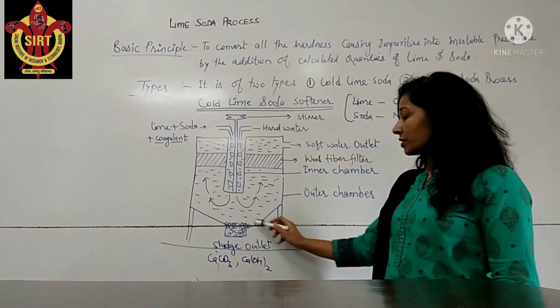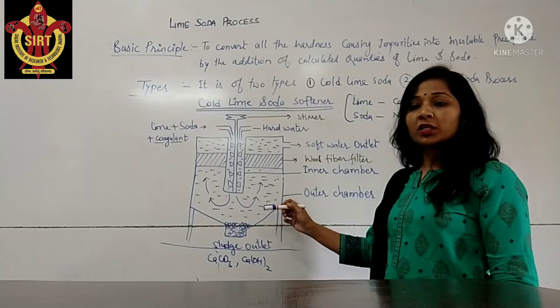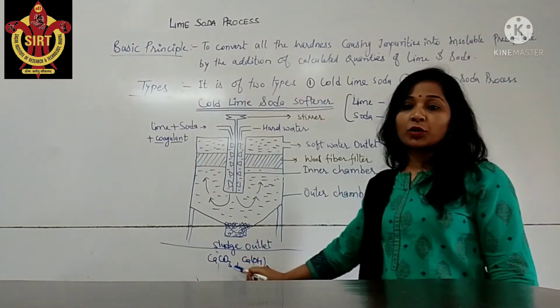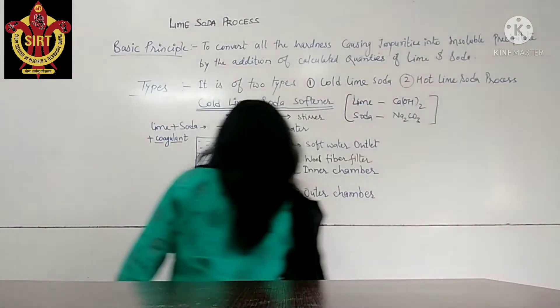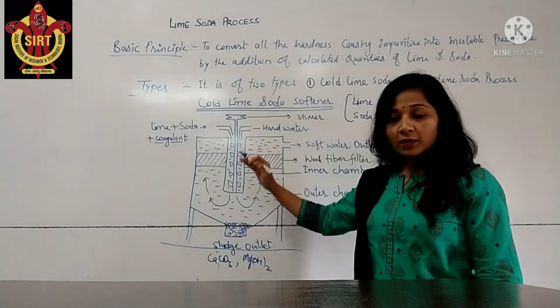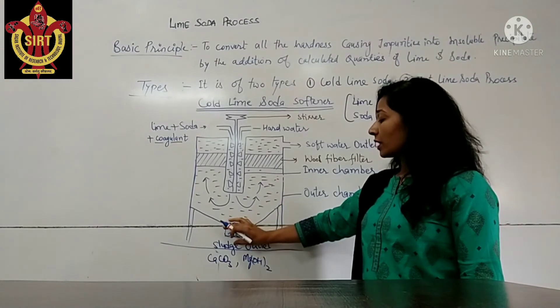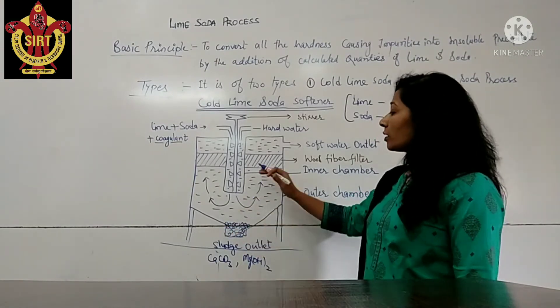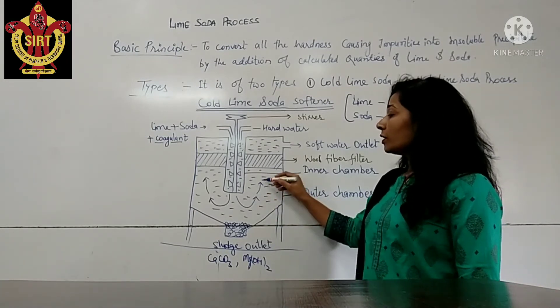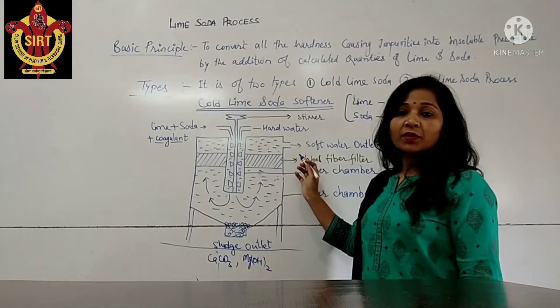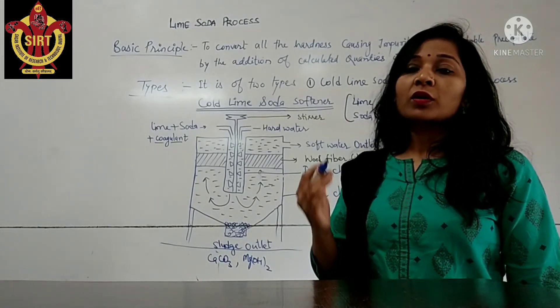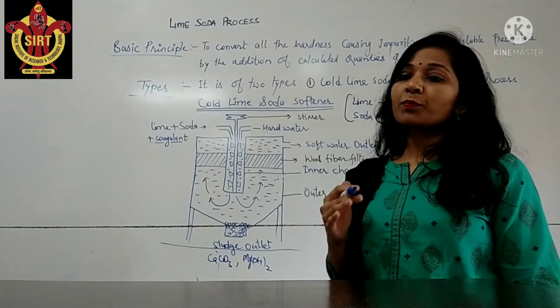In the outer chamber there is a sludge outlet, which is used for the collection or accumulation of the precipitate. The precipitate formed is in the form of calcium carbonate and magnesium hydroxide. Water from the inner chamber rises up through the outer chamber; the precipitate accumulates at the sludge outlet while water moves upward. When it moves upward, it passes through a wood fiber filter, which is used to ensure the complete removal of sludge and suspended impurities present in the water.